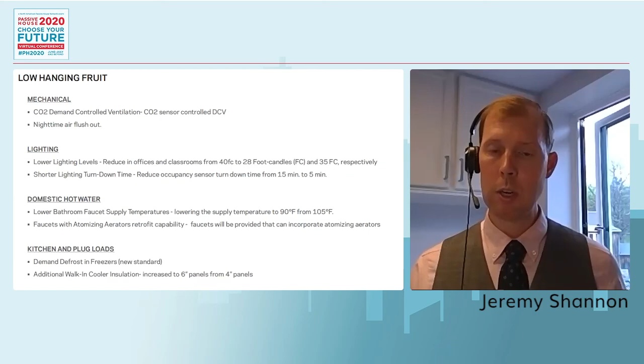So if anybody had a complaint about that space, it could be reprogrammed on the control side to raise that. On the domestic hot water side, we also had a really exciting win. We were providing 105-degree temperature to the lavatories in the bathrooms, and you're allowed to go down to 85 degrees for those sinks, and it's still comfortable for people to use. So we picked 90 degrees. We didn't go to the bottom, and it's a no-cost, huge savings.